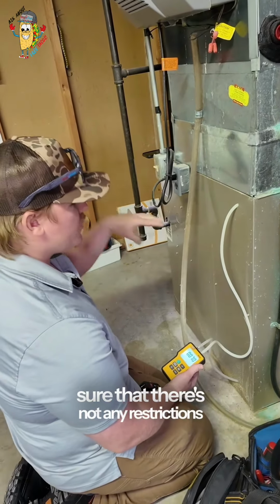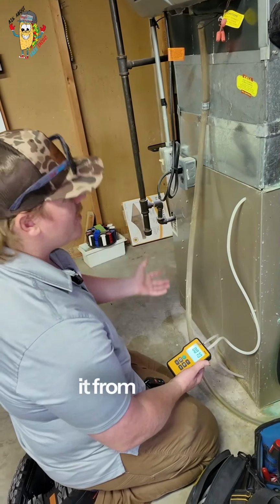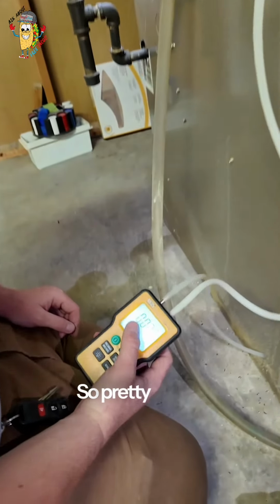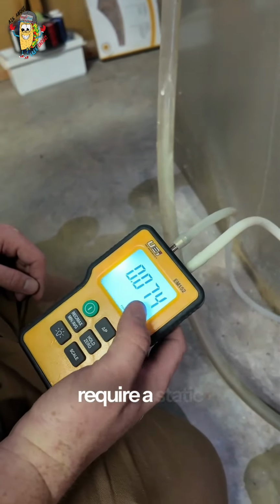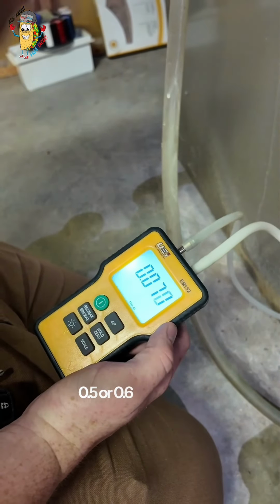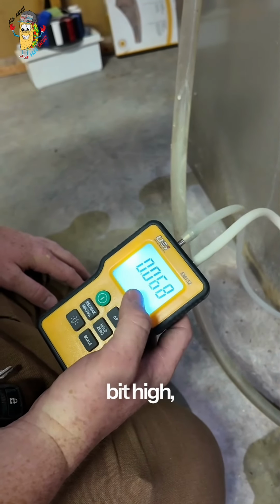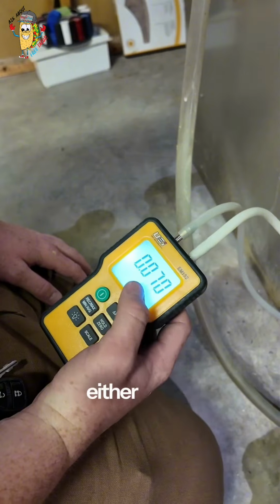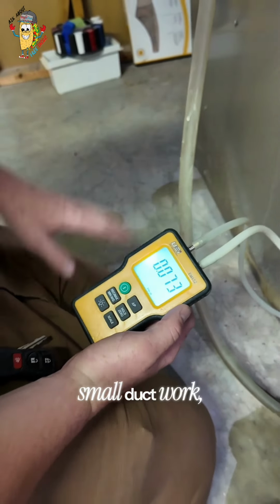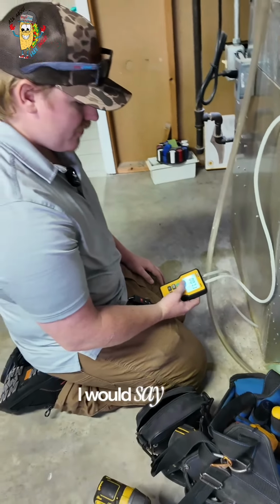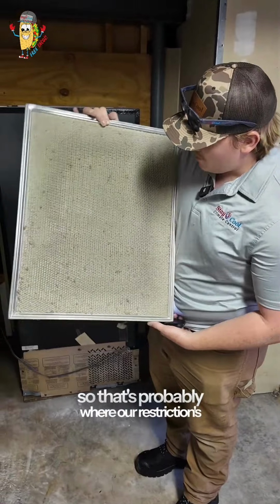that there's not any restrictions or things that are going to prevent it from getting up to the home where it needs to be. So pretty much most systems require a static pressure of around 0.5 or 0.6 maximum. This one's a little bit high, so most likely it has some kind of restriction, either a dirty filter, small ductwork, dirty coil, it could be several things. I would say that's pretty dirty, so that's probably where our restriction is going to be.